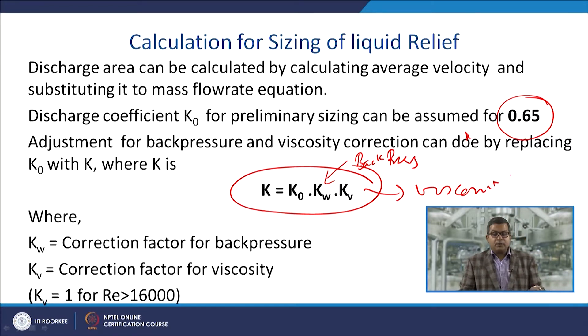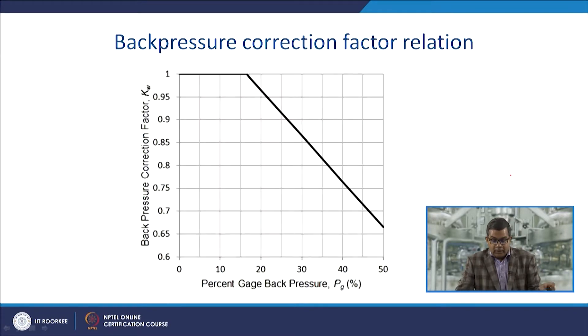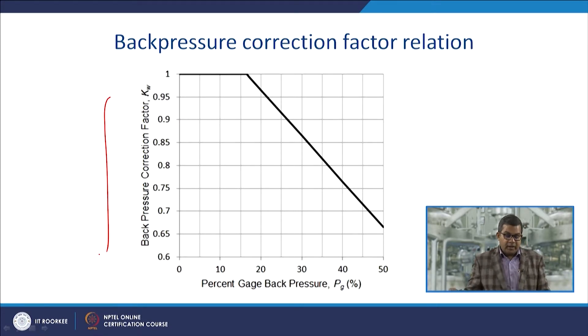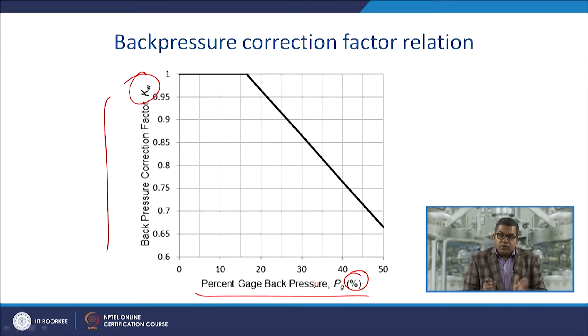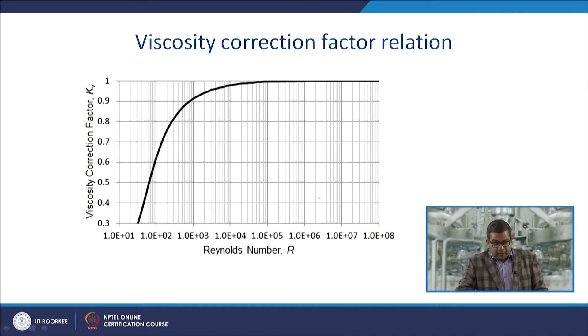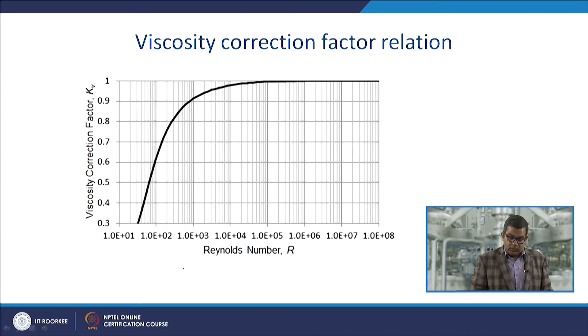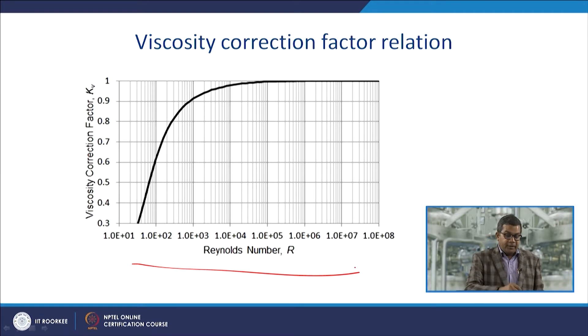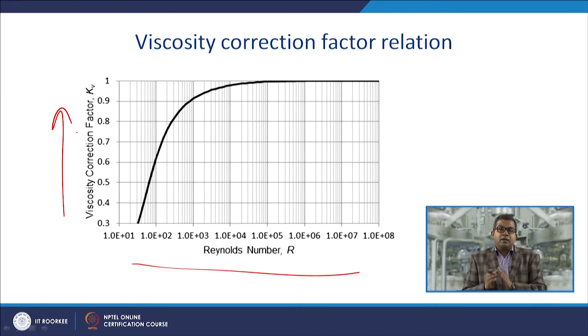The back pressure correction factor Kw relationship and the viscosity correction factor Kv relationship are shown in standard plots. The x-axis for the back pressure plot shows the percentage gauge back pressure Pg, and Kw is read off the curve. For viscosity correction, the x-axis is Reynolds number and the y-axis is Kv, allowing calculation of Kv given knowledge of the Reynolds number.